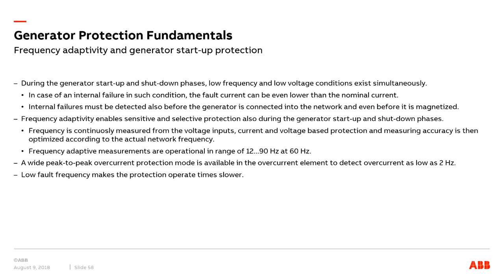It is important to have frequency adaptivity during generator startup and also during shutdown phases, because during those situations a low frequency and low voltage condition exists, which is a normal thing, not because of a fault. So in case of an internal failure in such a condition, the fault current can be even lower than the nominal current. Okay, and also the internal failure must be detected before the generator is connected into the network.